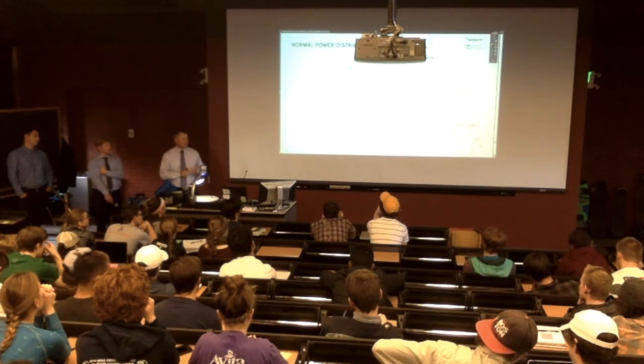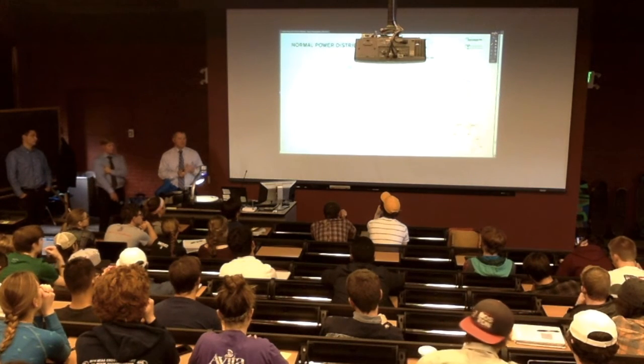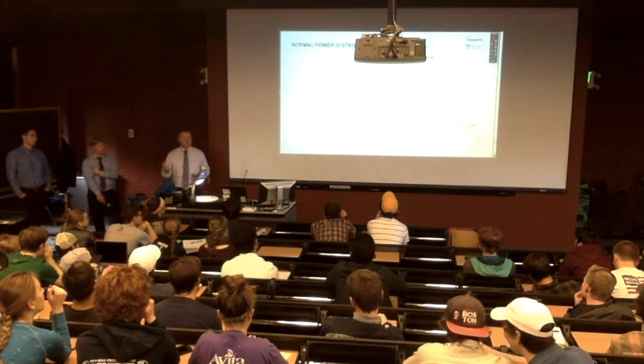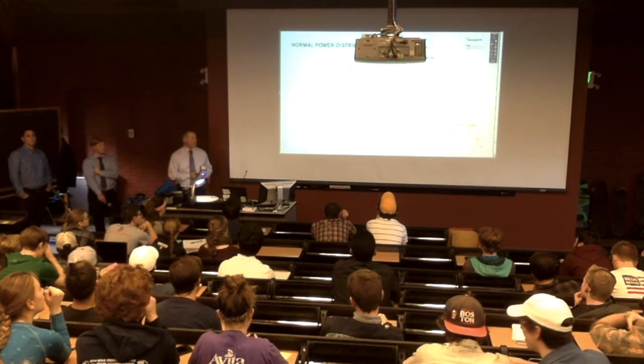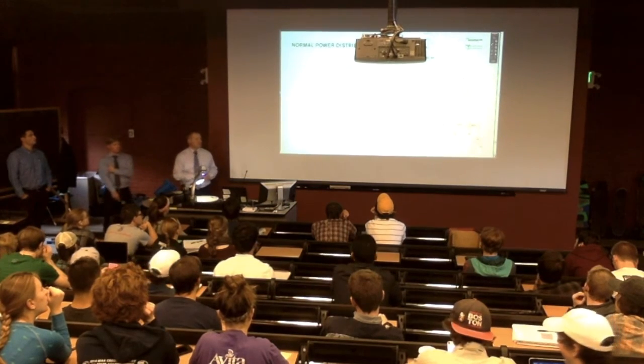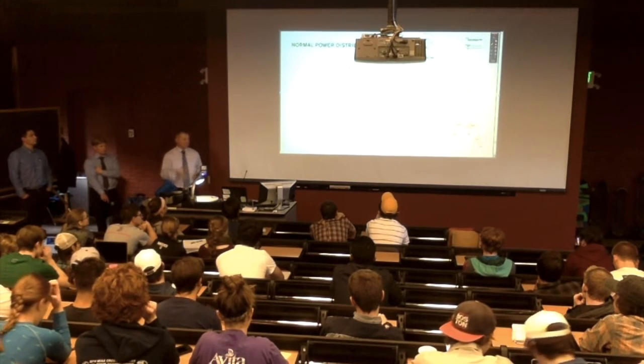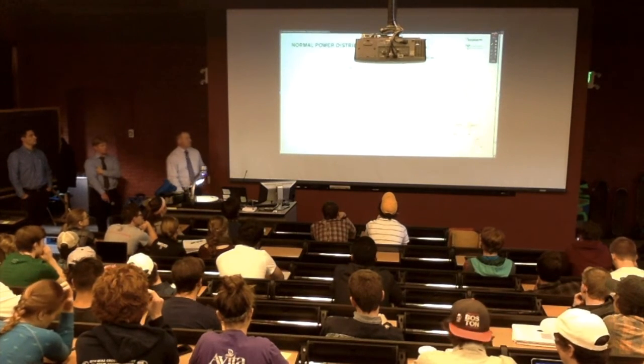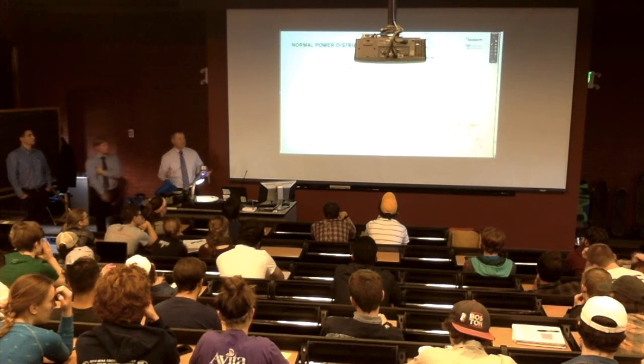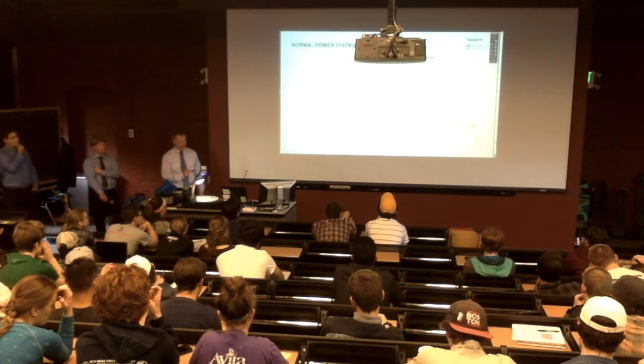So as an example, most of the building gets split up into three different components. One is the building equipment branch, which includes all the HVAC loads. There's also the lighting branch, which is 277 volt generally, although that's changing with the LED lighting. And then there's the plugs that go into the walls all around the building or onto the bench tops. So electrically, you have to figure out what the loads are and kind of back it all the way down, similar to the HVAC side. You have to design it all the way through.